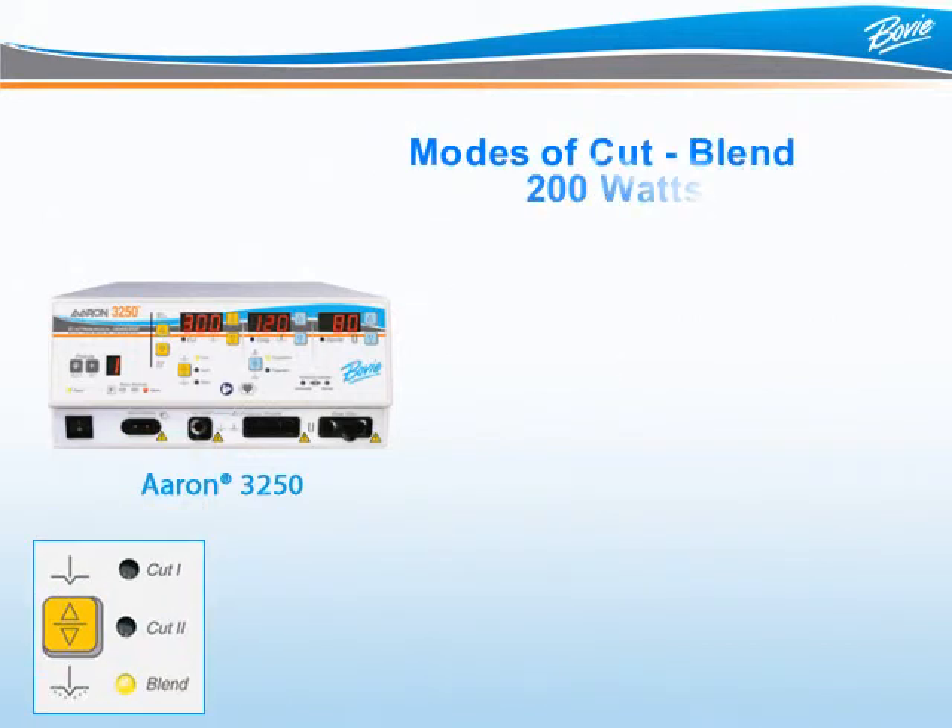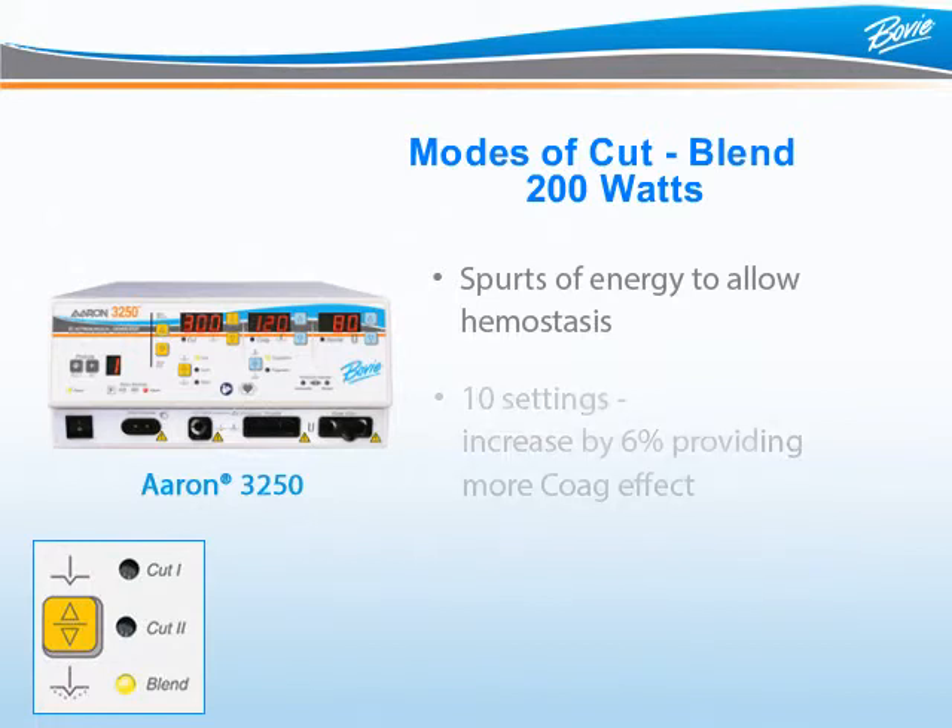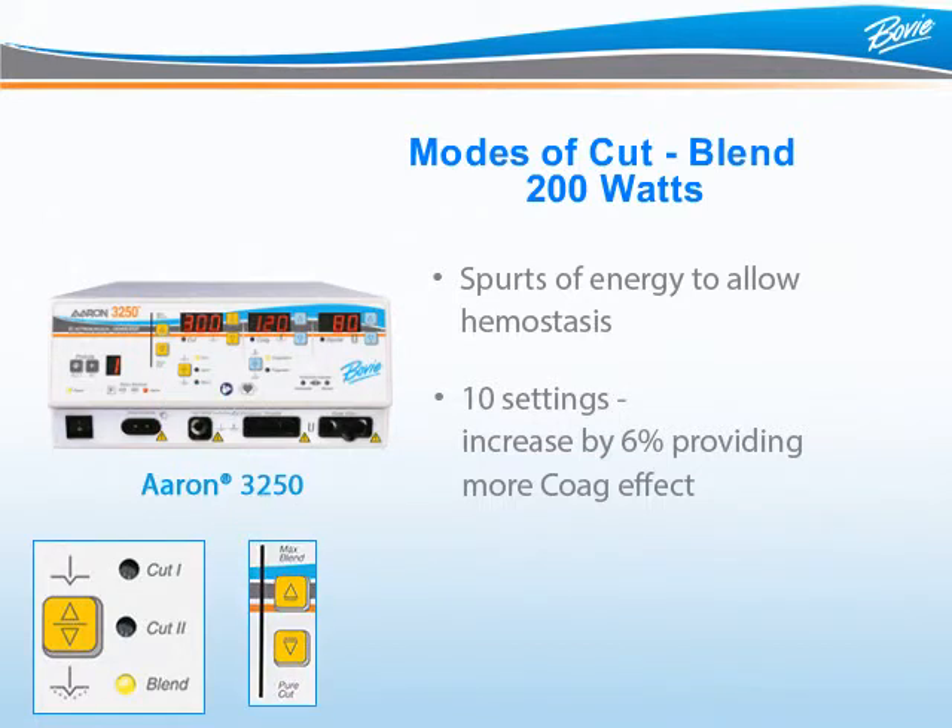Blend is a mode of Cut that delivers energy in spurts. In between the spurts of energy is a cooling period that allows for natural hemostasis or coagulation. The Aaron 3250 offers 10 blend settings with up to 200 watts of power. Each level of blend is increased by 6%. The higher the blend setting, the longer the cooling period and the more natural coagulation. To adjust the settings, use the up-down button next to the vertical LED bar. This level of versatility allows the surgeon to achieve the desired tissue effect in a very precise manner.